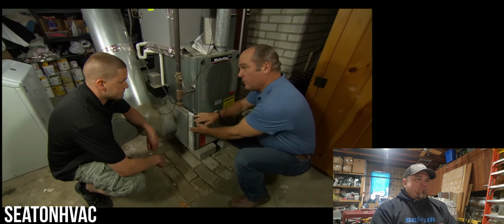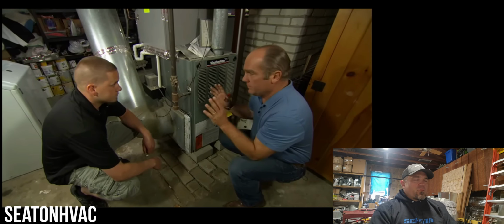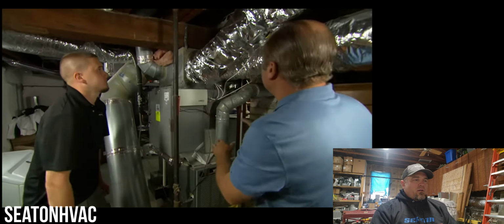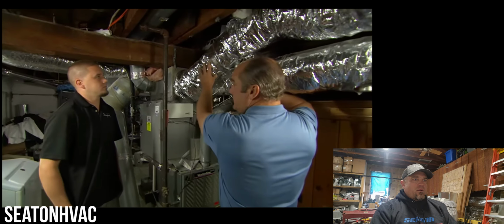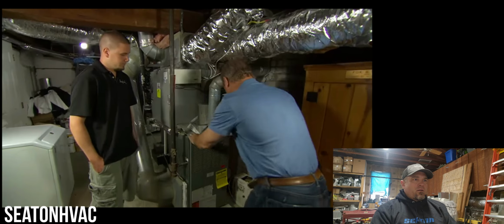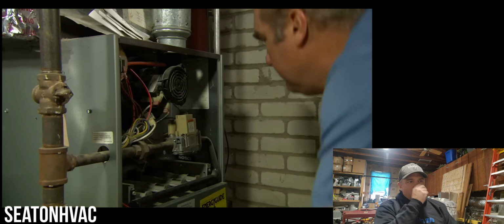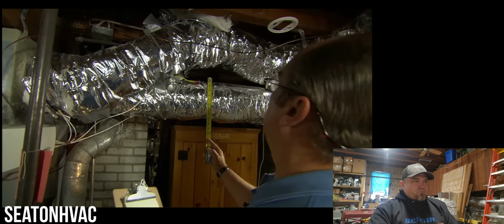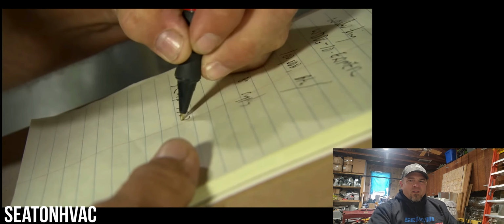Something simple like the return air filter clogged, you got to look at some other things and do a deeper evaluation. I want to check the ducts, the size and number of these ducts, and also what you have for equipment. So it looks like there's a motorized damper on one of those supply runs. So I don't know if it's zoned or what's going on here. They didn't get into any of that, so there might be an issue there too. Not sure what he's writing down, just the size of the ducts here, whatever.